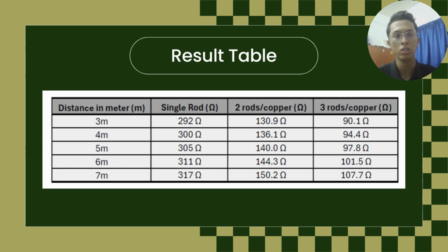Moving on to our primary findings, this result table illustrates the relationship between the distance of the grounding rods and the measured resistance in ohms. We have tested three different configurations, which are a single rod, two rod copper, and three rod copper, across a distance range of 3 to 7 meters. If you look at the data, you will notice two very clear trends. Number one is distance correlation. Regardless of the configuration, as the distance increases from 3 meters to 7 meters, the resistance also increases. For example, in the single rod setup, resistance climbs from 292 ohm to 317 ohm.